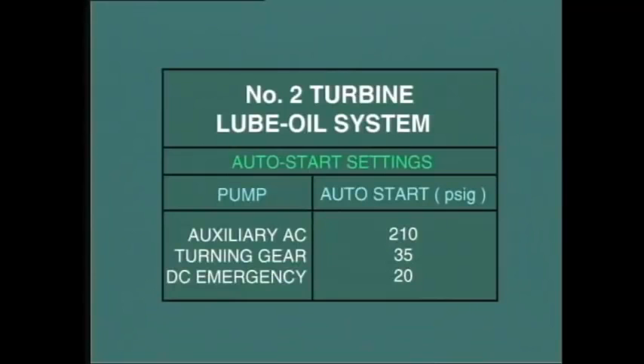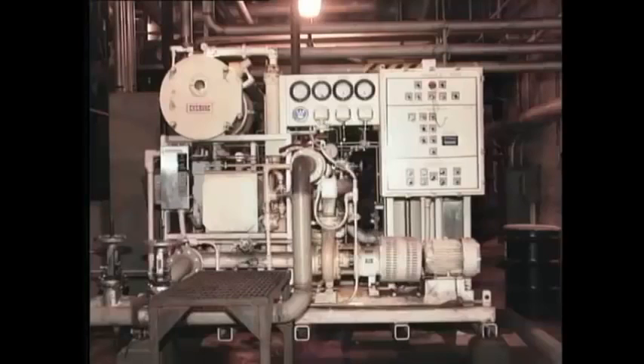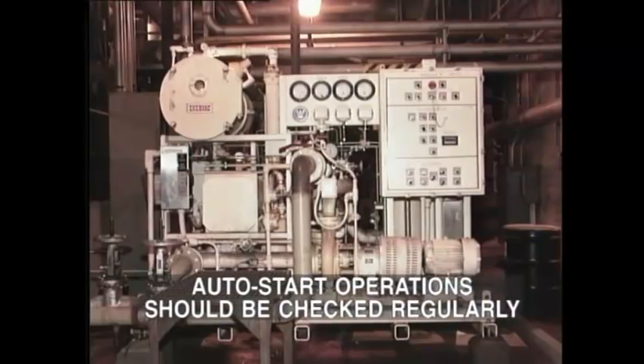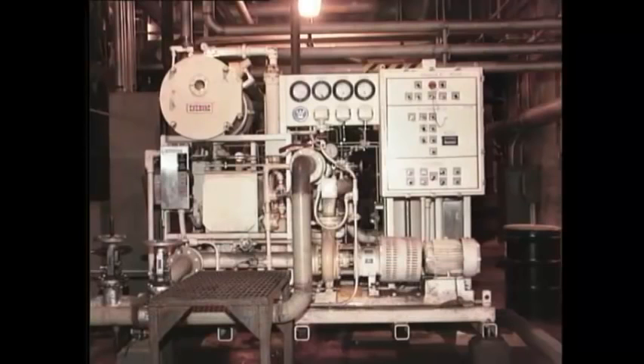So we can see that there is in fact a hierarchy of oil pumps with automatic startup based on pressure readings. If the high pressure oil pump fails and the pressure falls, the AC auxiliary oil pump will cut in automatically. If the lube oil pressure falls, the turning gear oil pump starts up automatically. And if this consequently fails, the DC oil pump will start. As with all automatic devices, the pump auto start operations should be checked on all pumps regularly. Make sure that you check out the details of your own lube oil and hydraulic oil systems. You should be thoroughly familiar with the location of all pumps and controls for these pumps.